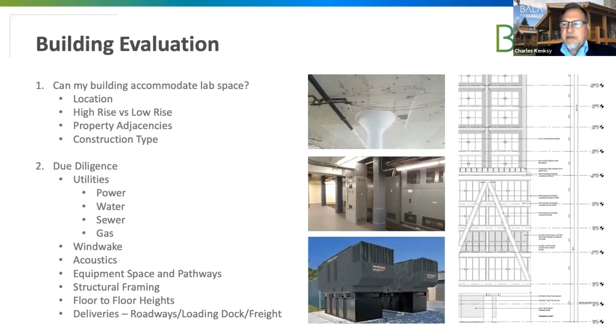Does the building have emergency power? A lot of buildings will have a small life safety generator. That's different from emergency power that's going to be running major equipment. We need to keep the exhaust fans and makeup air running for hoods and animals and different lab scenarios, so we've got to put that equipment on a generator. It's not a life safety generator—it's a standby emergency generator.